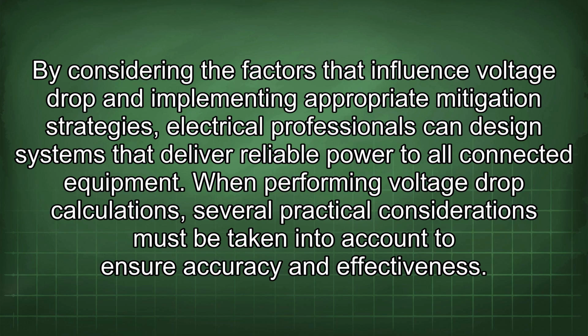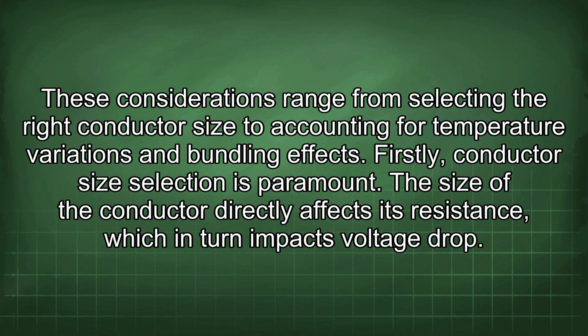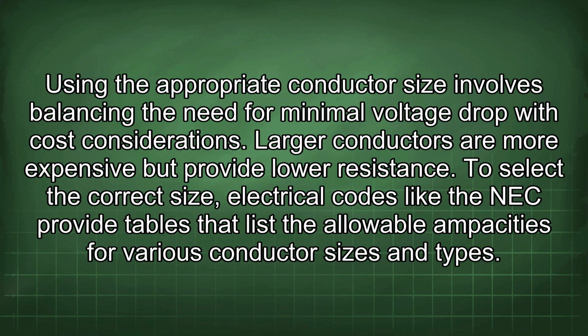When performing voltage drop calculations, several practical considerations must be taken into account to ensure accuracy and effectiveness. These considerations range from selecting the right conductor size to accounting for temperature variations and bundling effects. Firstly, conductor size selection is paramount. The size of the conductor directly affects its resistance, which in turn impacts voltage drop. Using the appropriate conductor size involves balancing the need for minimal voltage drop with cost considerations. Larger conductors are more expensive but provide lower resistance.